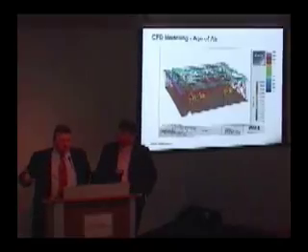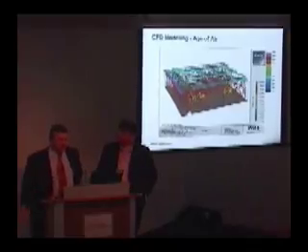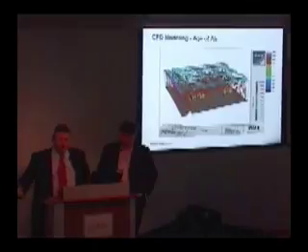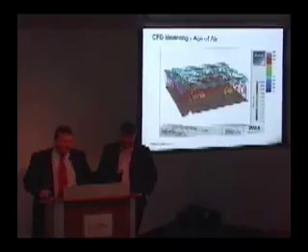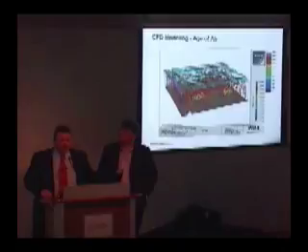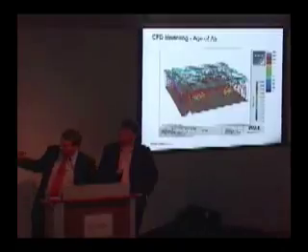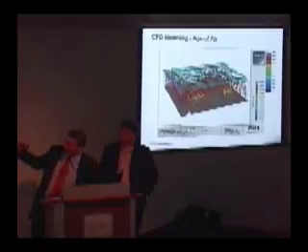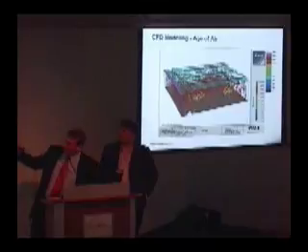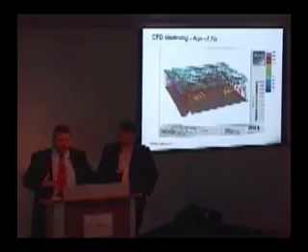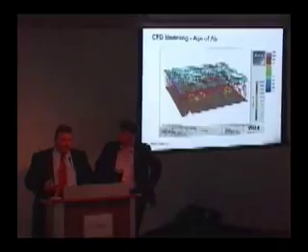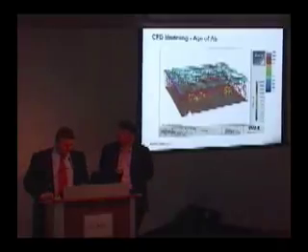There was concern from our client that air coming from the floor diffusers and being pulled back to the wall would short-circuit — that it wouldn't condition the space but instead be drawn immediately into the outside wall. We modeled this and were able to show the age of air in the space. The model shows that the age of air being mixed in the space is roughly the same as the age of air in the double-wall cavity, and that modeling helped us prove that the system works as intended.